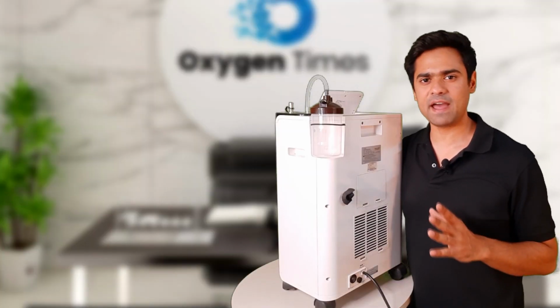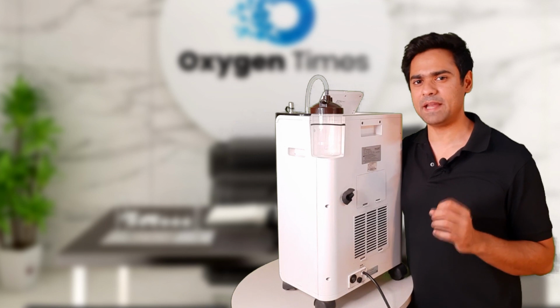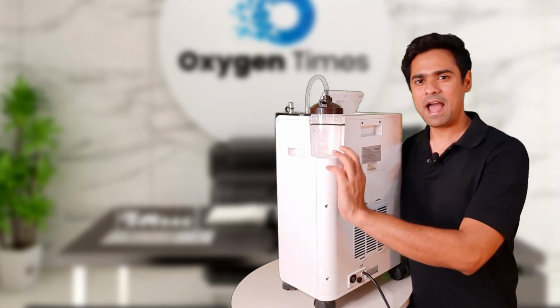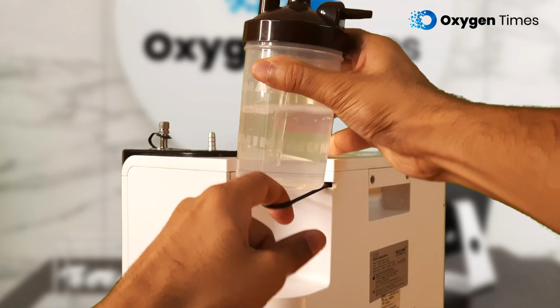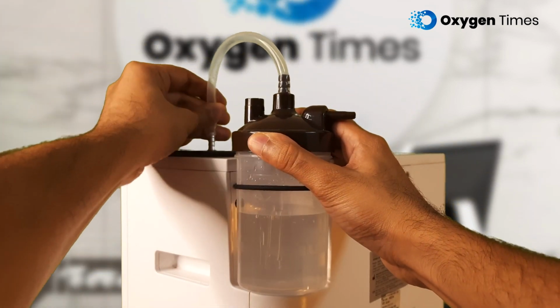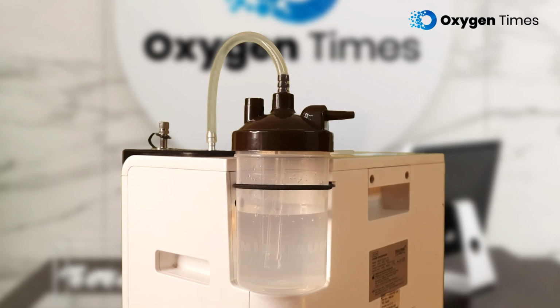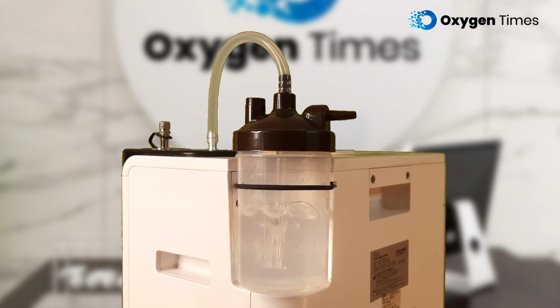Moving on, the humidifier bottle can be conveniently placed in the elastic strap and the tubing can be attached to the oxygen outlet without much effort. As we switch on the machine, we saw bubbles being formed in the humidifier water bottle, indicating that the oxygen is coming out of the oxygen outlet.